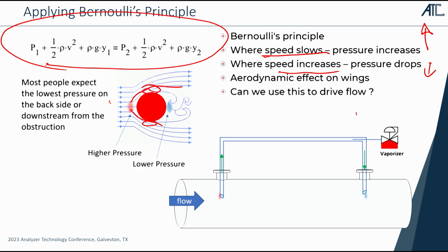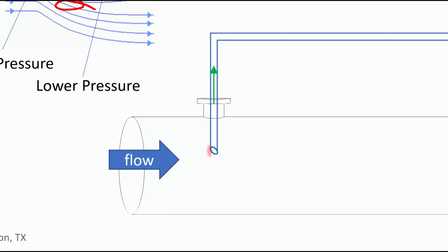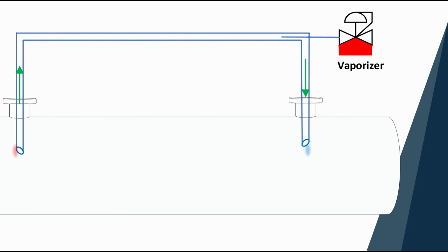This principle has been applied by a bunch of people. There are ExxonMobil patents that have talked about this sort of idea. Shell has looked at this for LNG vaporization in a system that's sort of like the one I show at the bottom here. Commonly, in systems like this, if the direction of flow is coming in, they cut a probe angled towards the direction of flow. The flow impacts on that, drives its way up through that piece of tubing, and runs across. They have another probe cut at the opposite angle, away from the direction of flow. It creates a low pressure zone, and now you can get continuous flow through that loop and vaporize that flow. It gives you faster response at the vaporizer. However, it may not be the best use of the energy and the capacity of that pipe to actually generate differential pressure and flow. So we're going to talk a bit about how we can optimize a system like this.